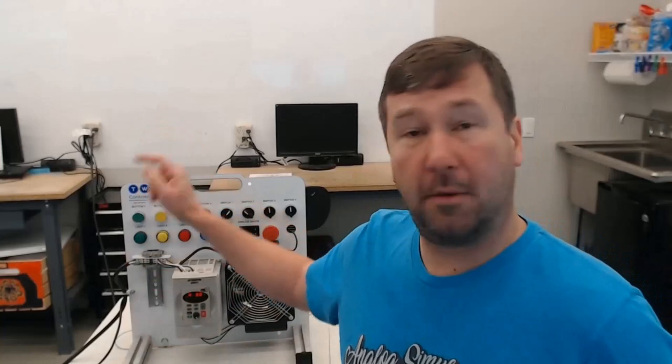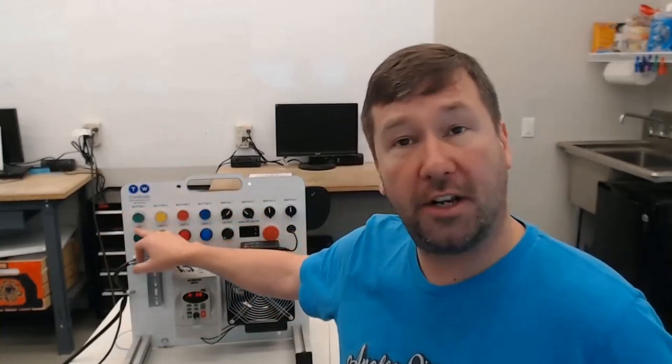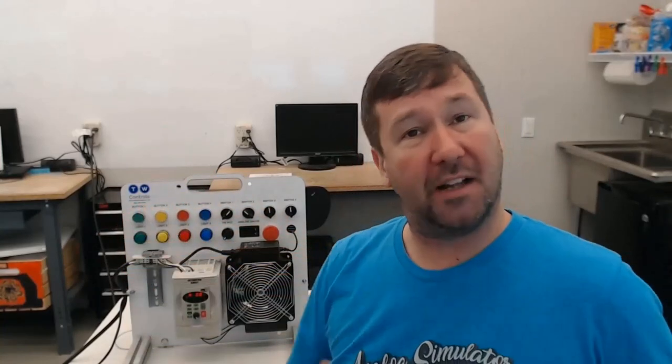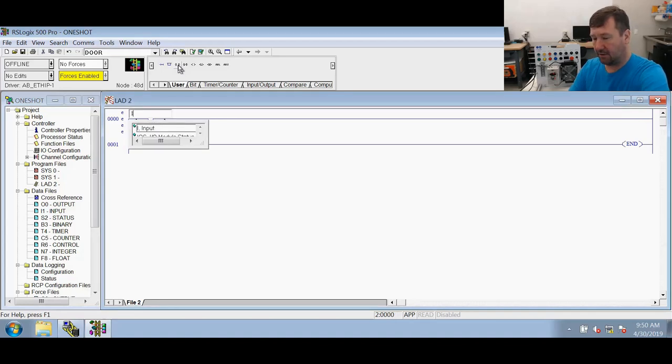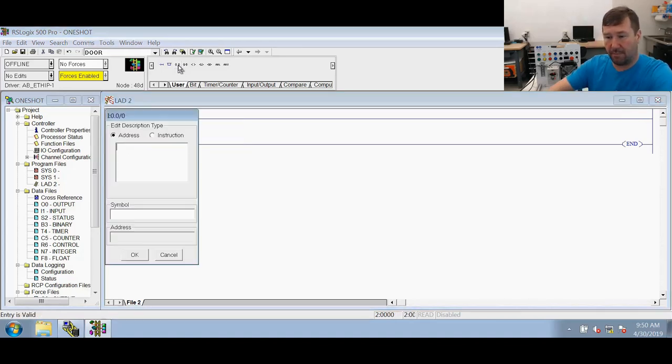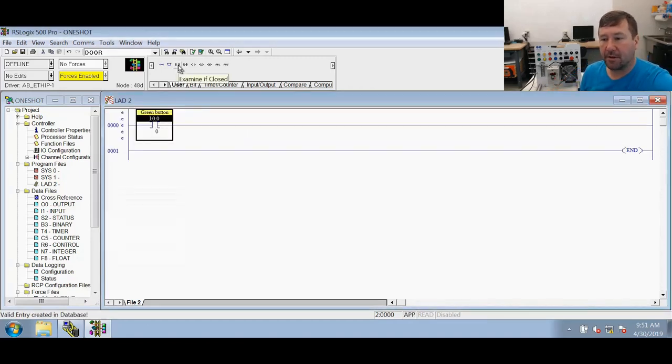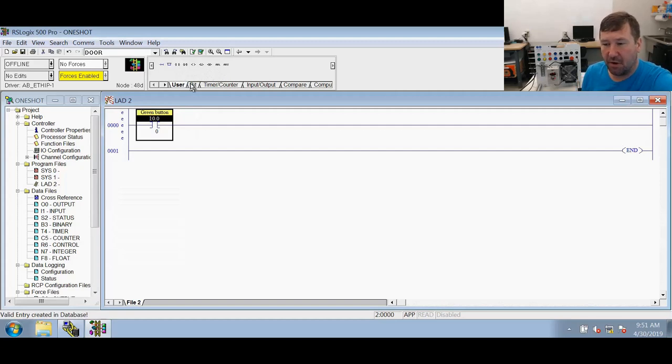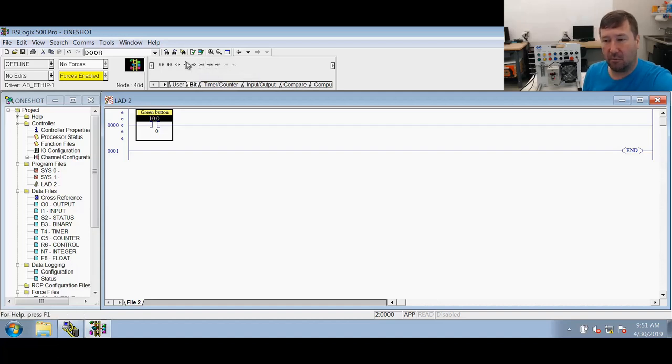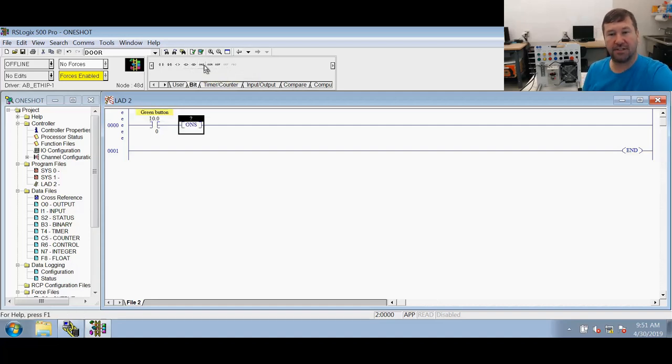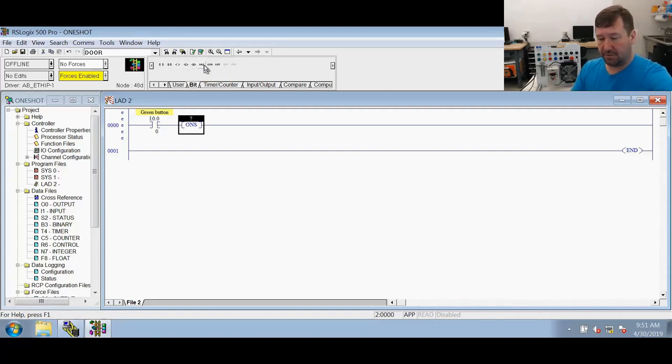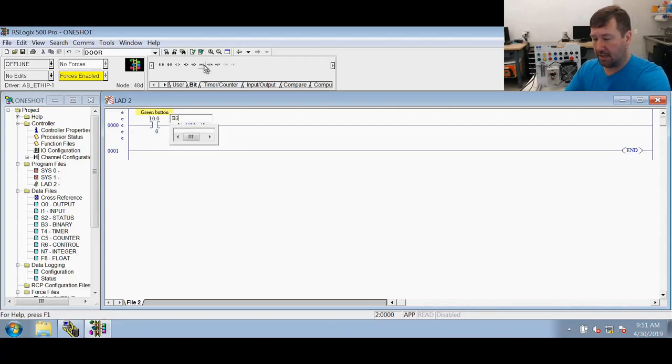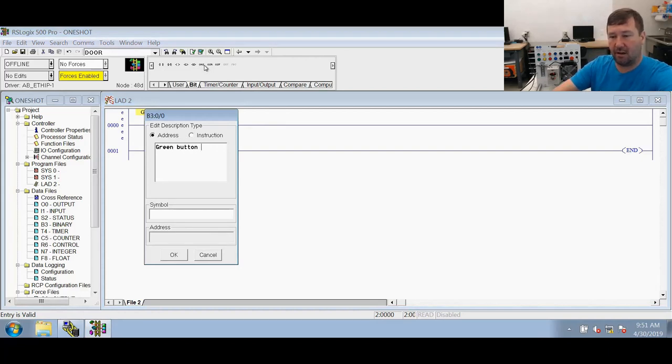So we're going to be using the green button to turn on and off the green light. Same button, this is sometimes called a flip flop. We're going to use an XIC instruction of I colon zero backslash zero which is that green button. And then we are going to use an ONS instruction. If you go over here under bits you have our basic ones, you have our latches, and you have our three one shot bits. And we're going to use the ONS one shot bit. Now an ONS one shot bit has one bit associated with it and we'll just use B3 colon zero backslash zero. And let's just call that the green button ONS.